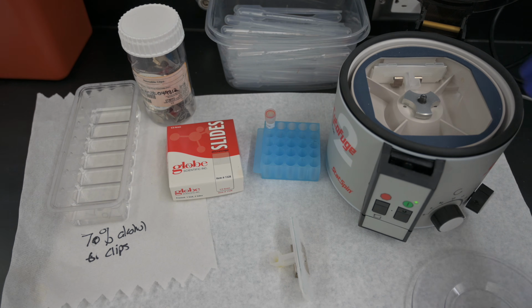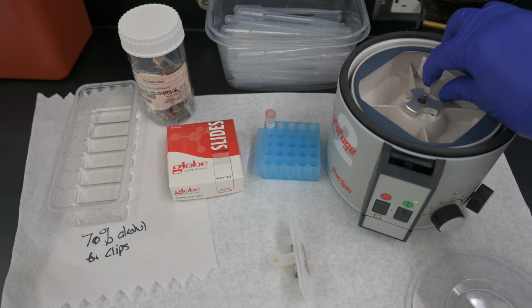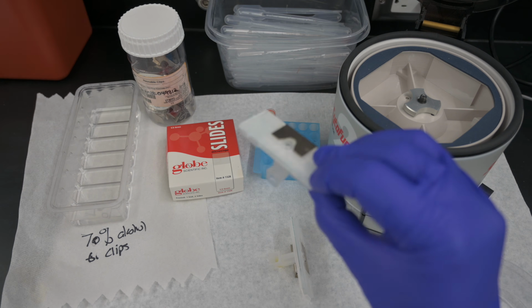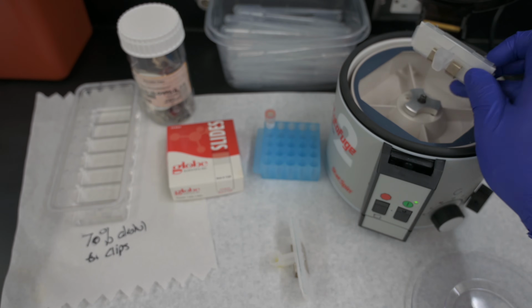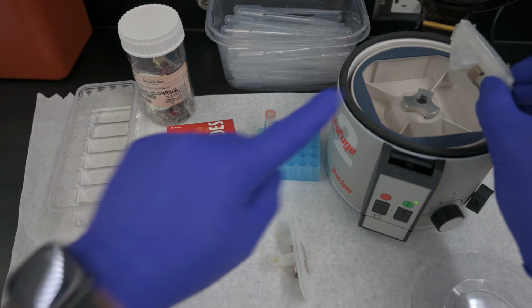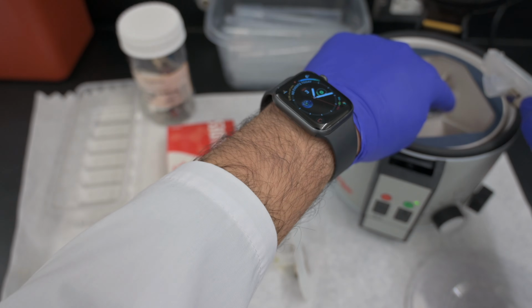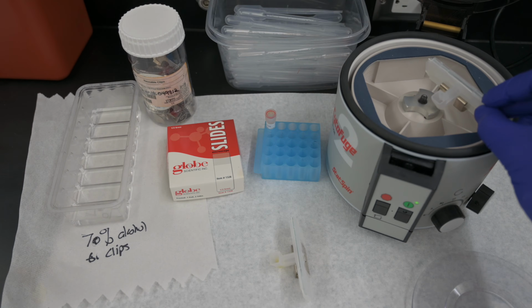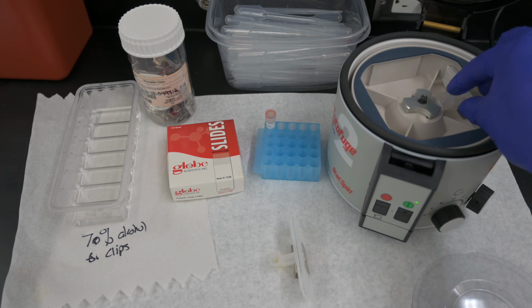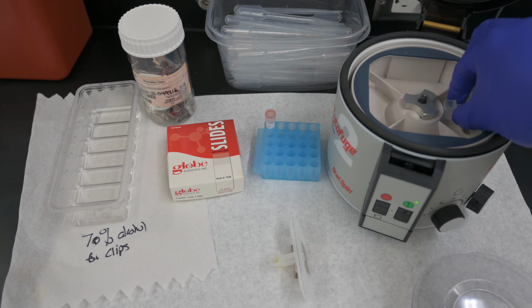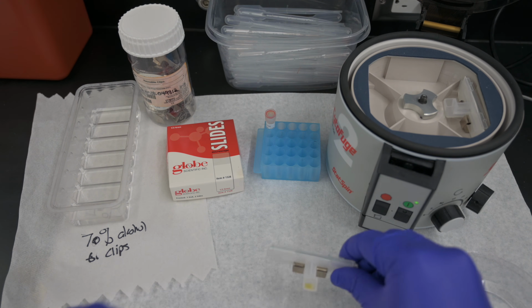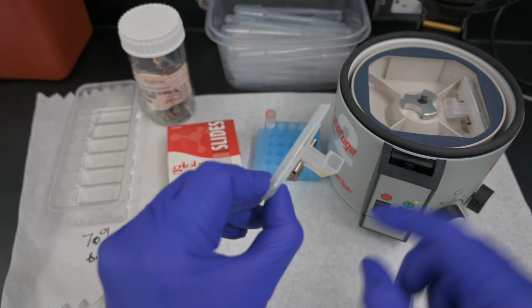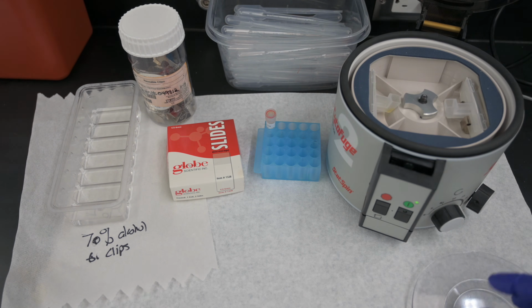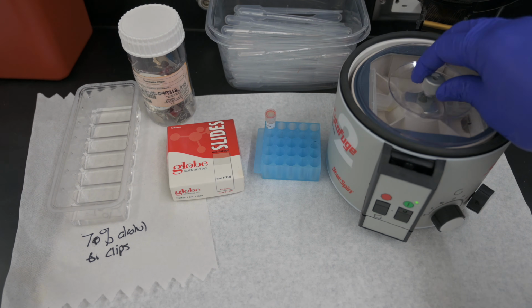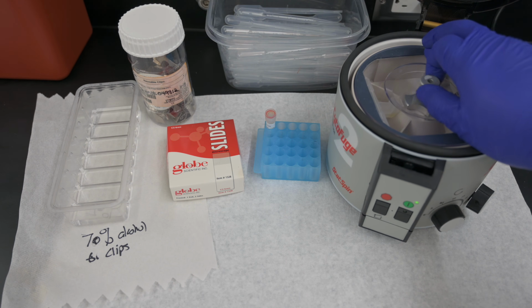We're going to remove the safety shield, and of course our centrifuge needs to be balanced. So this assembly that I'm holding here is the balance assembly, complete with the clip as well as a microscope slide. The funnel needs to face towards the rotor. That allows it to sit on an angle, again, to prevent the fluid from coming into contact with the slide prematurely. So I'm going to place the loaded assembly directly opposite of that balance assembly, placing the safety shield back into place, screwing that down firmly.